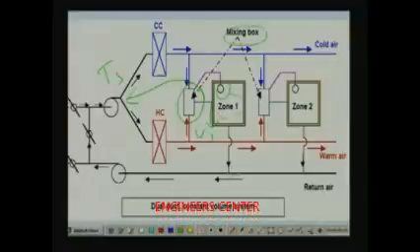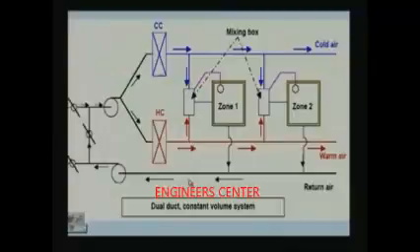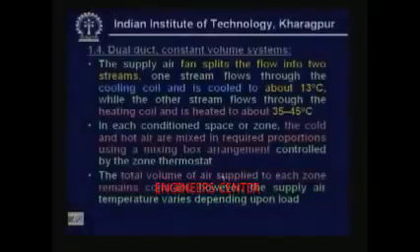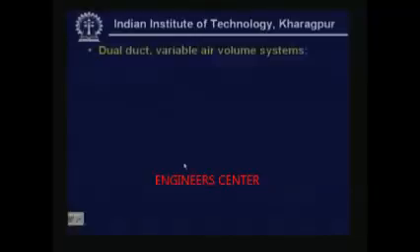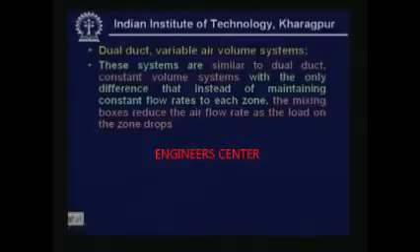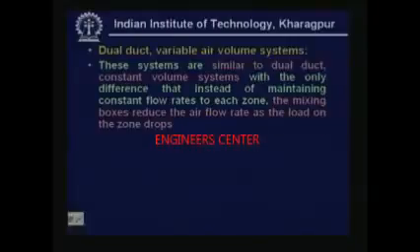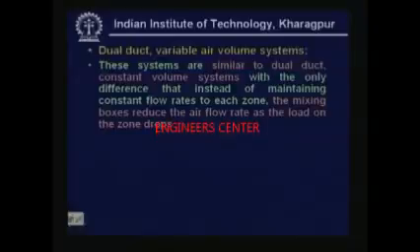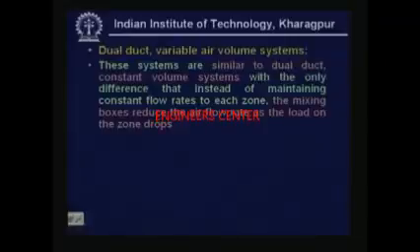The return air is sent back to the system using a return air duct. So this is a dual duct constant volume system. We can also have a dual duct variable air volume system. As the name implies, here the temperature is kept constant but the volume is varied. These systems are similar to dual duct constant volume systems, with the only difference that instead of maintaining constant flow rates to each zone, the mixing boxes reduce the air flow rate as the load on the zone drops.